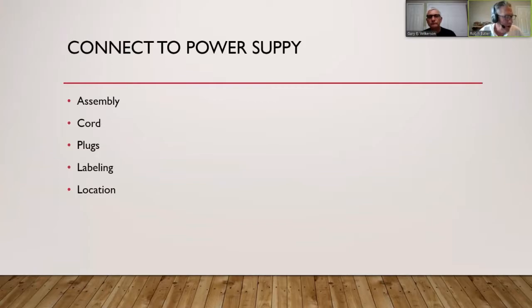With the 50 amp, you have two hot leads, an X and a Y, and each one of those would carry 120 volts. And they are the darker colored ungrounded conductors, what we call the hot wire. Normally, in NEMA and insulation standards, they make it red and black. So the manufacturer will supply something red and black, and you know that is your ungrounded conductors.